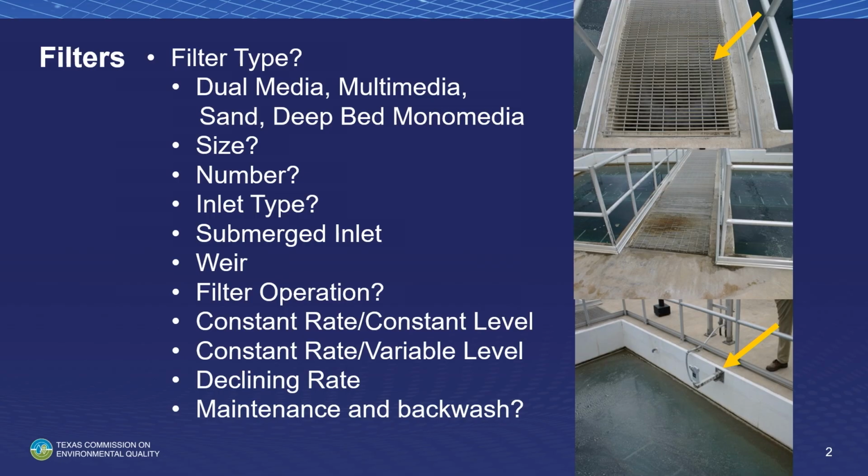Filter controls. We were working with a water plant down south of here many years ago, and when we were doing an MCPE, when we rolled up on site, their coagulant pumps were leaking, and their coagulant was running out of the door of the filter gallery down the street and into a ditch. Right away, we figured we were going to have a problem with this MCPE. So we finally got to the point where we did the filter inspection, and after you do a filter inspection, you know, they draw it down, we go down in it and clamber around, play in the sand, do our thing, come back up out of it and say, well, now we want you to do a backwash.